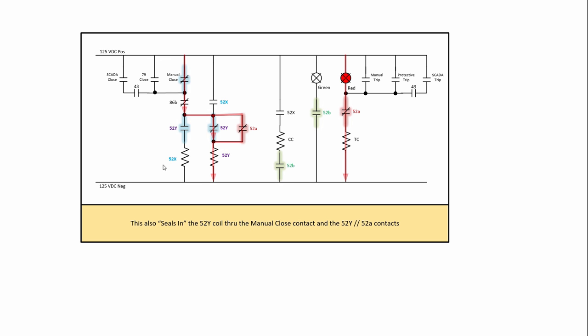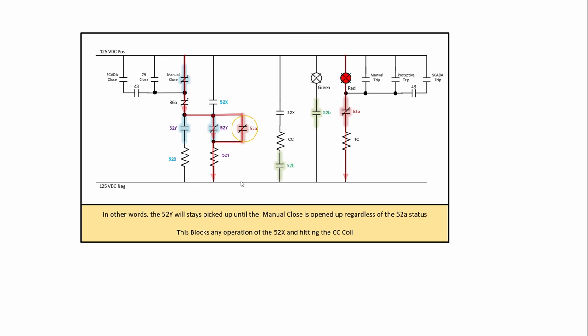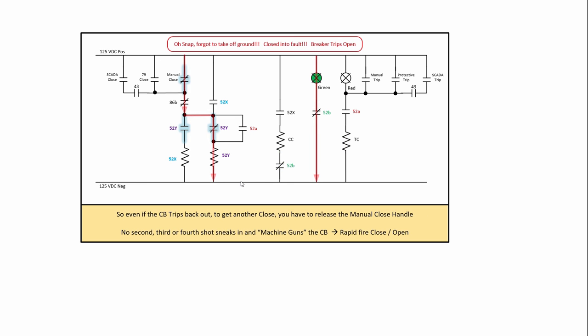So again, the seal in the 52Y coil through the manual close contact, as I just showed you, the parallel combination. Now, what's nice about that is if the 52A were to open again, i.e. you closed into a fault and it tripped out, nothing will happen. So, oh snap, we forgot to take the grounds off. Closed into a fault, breaker trips open. So the breaker opens but you still have your hand on the close handle and so everything is good and it won't let another close happen even though the breaker changes state.